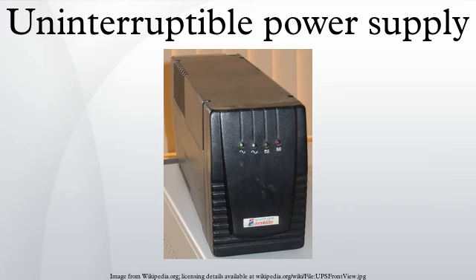Batteries. The runtime for a battery-operated UPS depends on the type and size of batteries, the rate of discharge, and the efficiency of the inverter. The total capacity of a lead-acid battery is a function of the rate at which it is discharged, which is described as Peukert's law. Manufacturers supply runtime rating in minutes for packaged UPS systems. Larger systems require detailed calculation of the load, inverter efficiency, and battery characteristics to ensure the required endurance is attained.